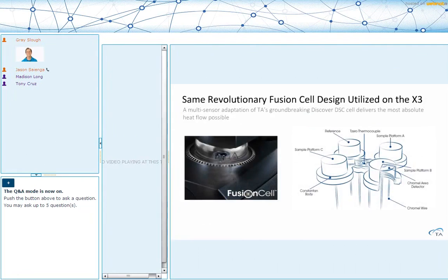It's built upon a similar or same fusion cell design that we utilize in our single sample sensors. Our Discovery DSC platform was the introduction of the fusion cell, and clearly this isn't the same cell. We have 4 pedestals, 3 samples, and a reference pedestal, but it's built upon the same independent heat flow measurement.